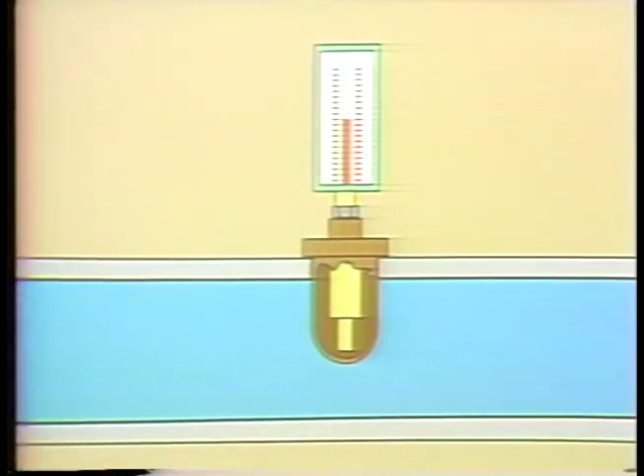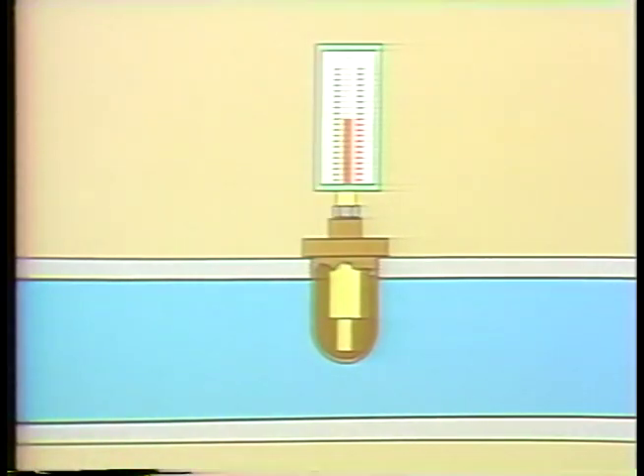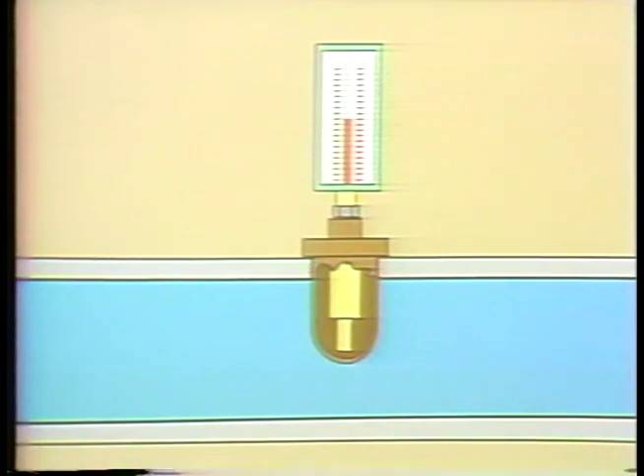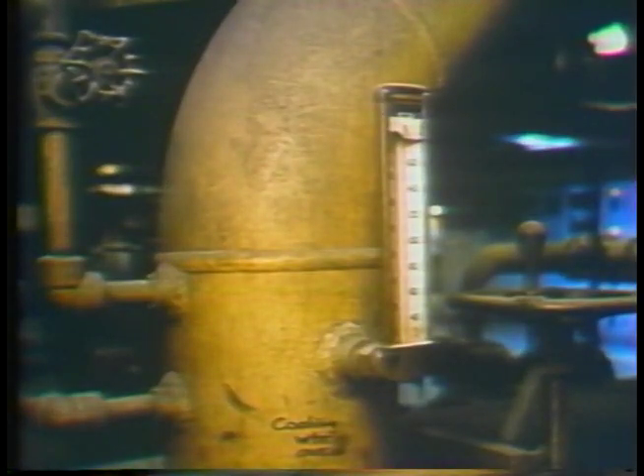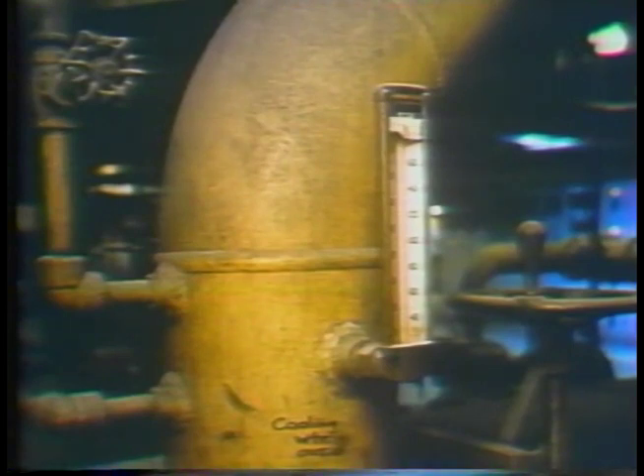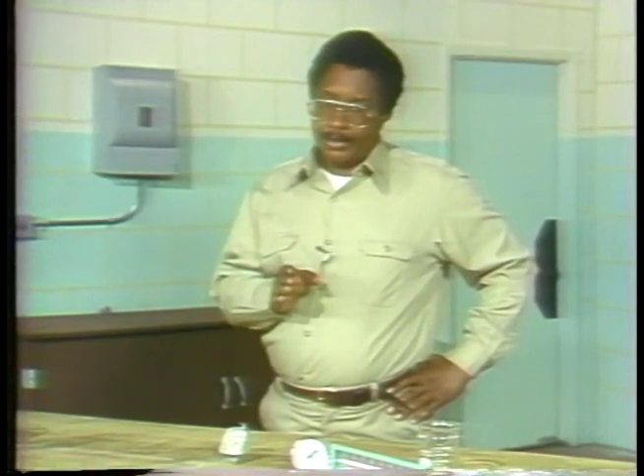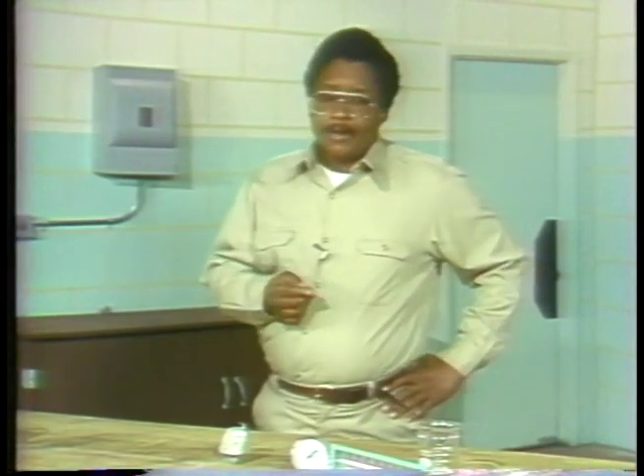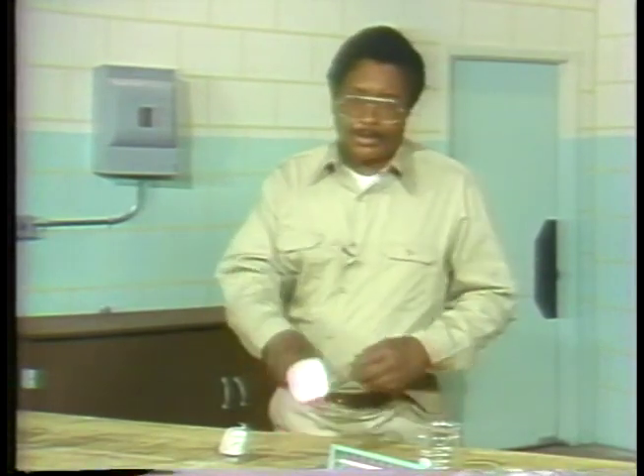One advantage of thermowells is that they allow for the easy removal and replacement of sensing elements for maintenance purposes. Thermowells can be used for almost all types of temperature measuring instruments. An example is this liquid-filled thermometer measuring the temperature of cooling water going to an oil cooler — the water cools oil returning from bearings and is a crucial factor in the operation of the bearing oil system. That's one of the advantages of liquid-filled thermometers: they are extremely accurate instruments, but they are also relatively fragile. For more rugged applications, bimetallic thermometers are often used.